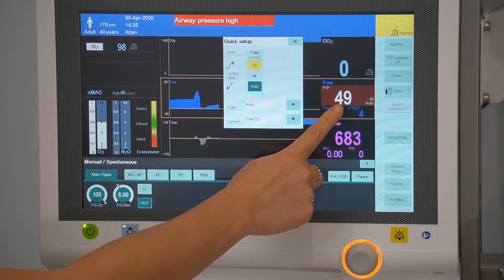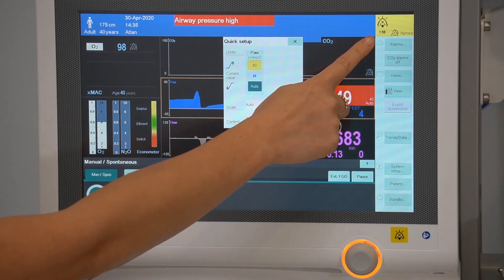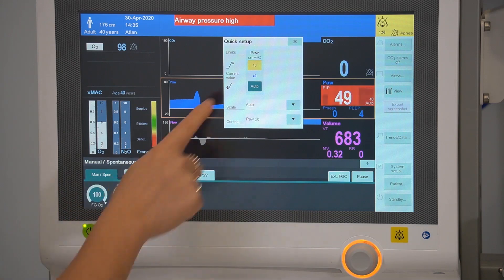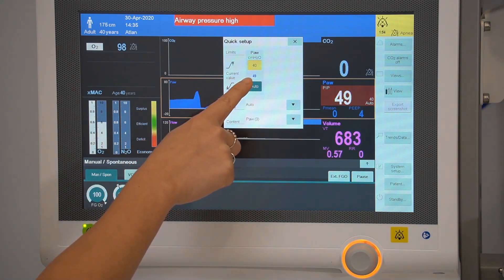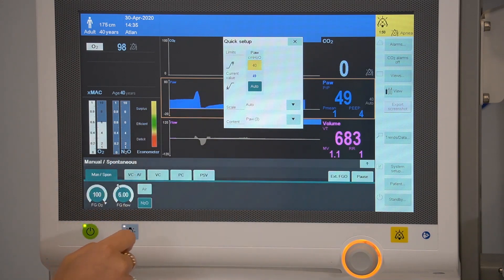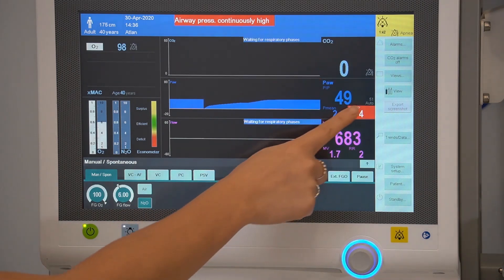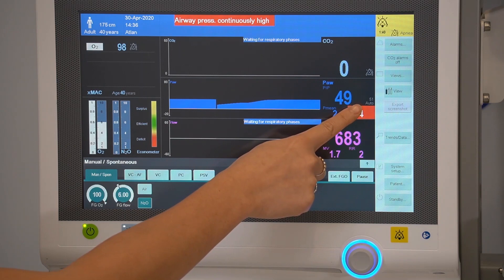When a parameter breaches the set alarm limits, you can use the silence button to silence the alarm for two minutes. The current value will be displayed here and the breached alarm limit will be highlighted allowing for easy adjustment of the alarm. Your new alarm limit will be displayed on the side.